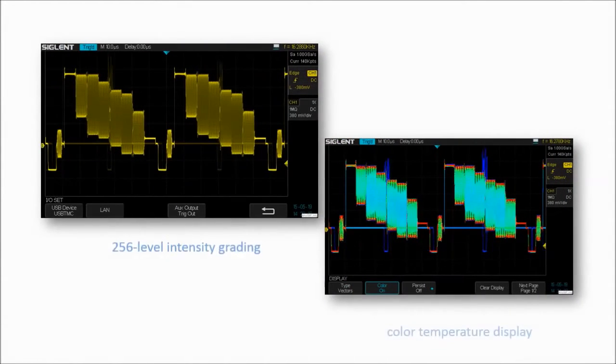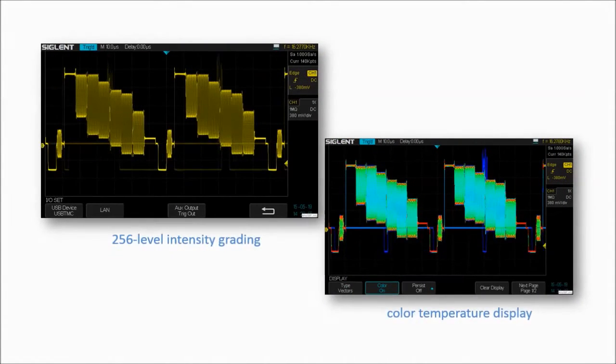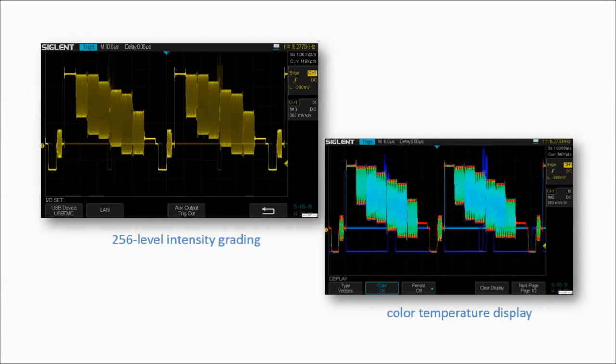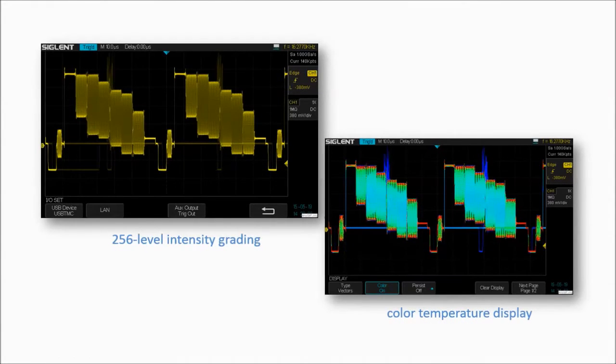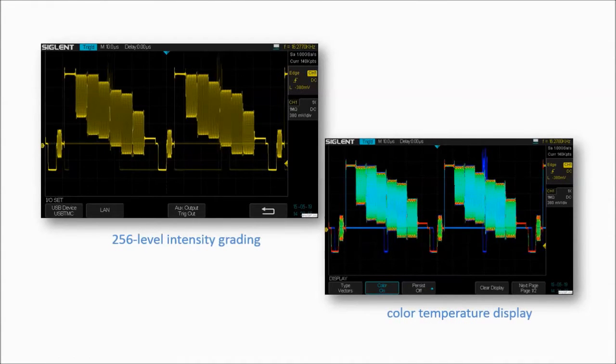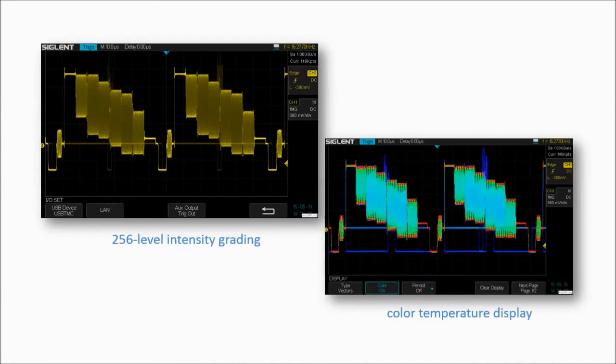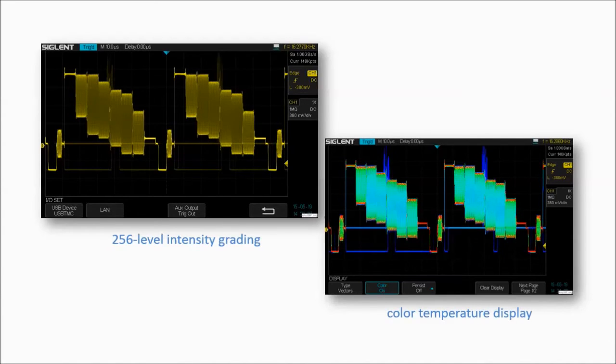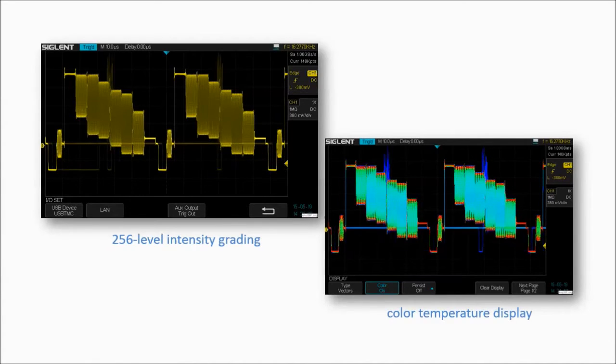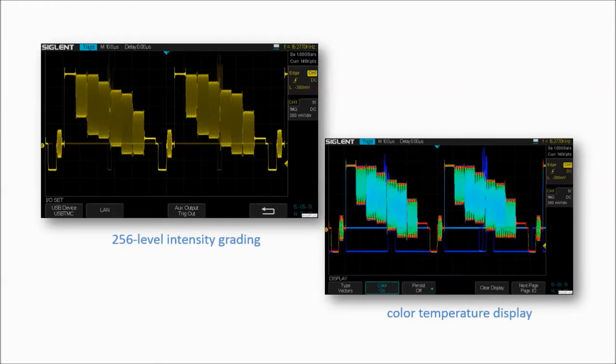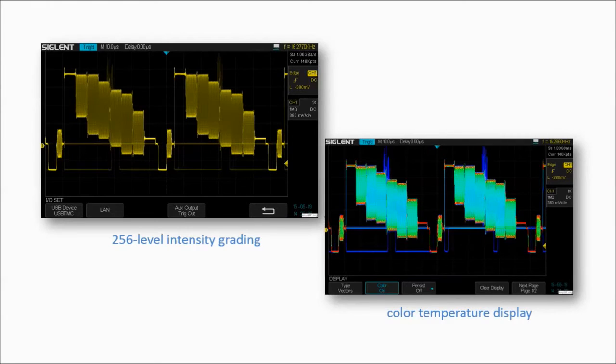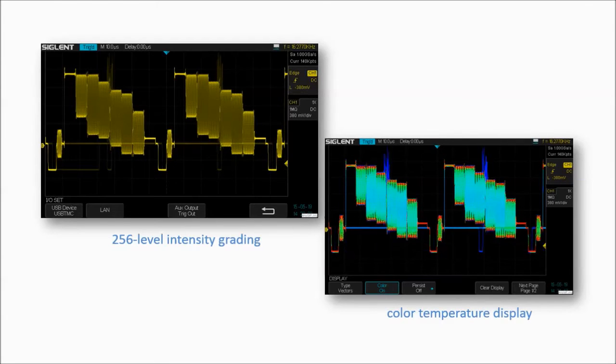The SDS1000X has a 256 intensity grading and color temperature display. SPO display technology provides fast refresh rates, and the resulting intensity grade trace is brighter for often occurring display points and dimmer in less often occurring points.